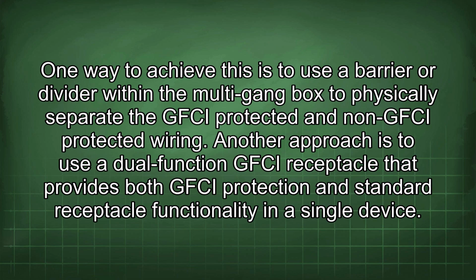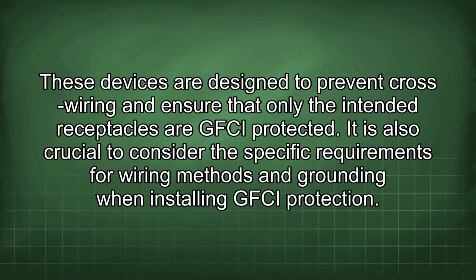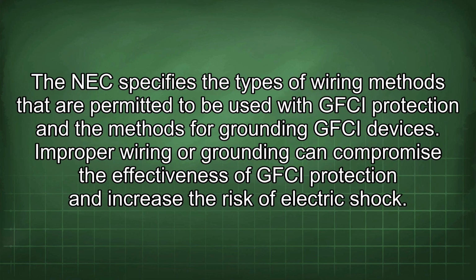Another approach is to use a dual-function GFCI receptacle that provides both GFCI protection and standard receptacle functionality in a single device. These devices are designed to prevent cross-wiring and ensure that only the intended receptacles are GFCI protected. It is also crucial to consider the specific requirements for wiring methods and grounding when installing GFCI protection. The NEC specifies the types of wiring methods that are permitted to be used with GFCI protection and the methods for grounding GFCI devices.